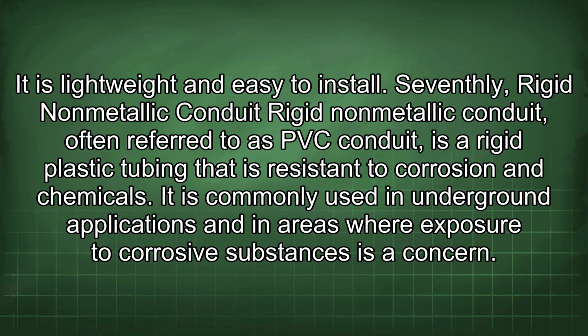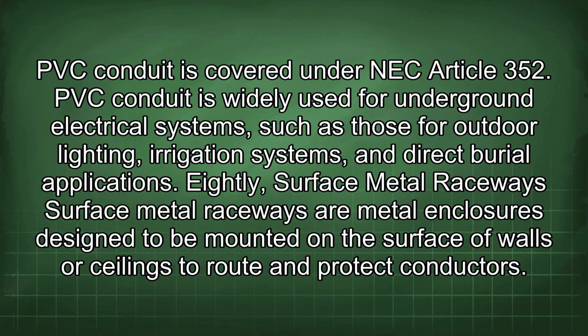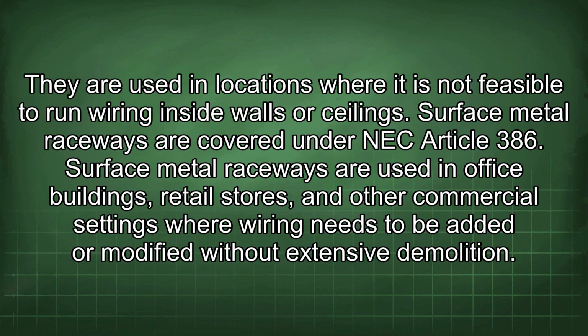Seventhly, rigid non-metallic conduit. Rigid non-metallic conduit, often referred to as PVC conduit, is a rigid plastic tubing that is resistant to corrosion and chemicals. It is commonly used in underground applications and in areas where exposure to corrosive substances is a concern. PVC conduit is covered under NEC Article 352. PVC conduit is widely used for underground electrical systems, such as those for outdoor lighting, irrigation systems, and direct burial applications. Eighthly, surface metal raceways. Surface metal raceways are metal enclosures designed to be mounted on the surface of walls or ceilings to route and protect conductors. They are used in locations where it is not feasible to run wiring inside walls or ceilings.